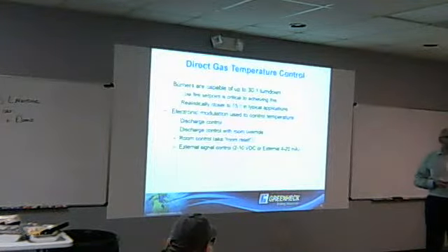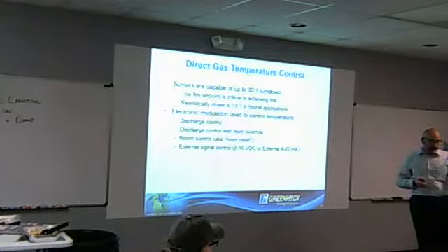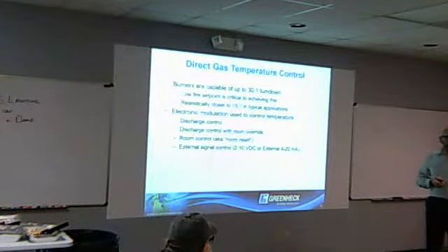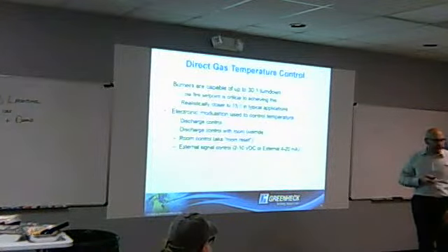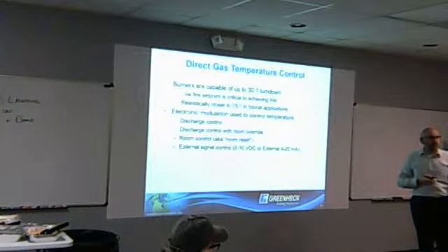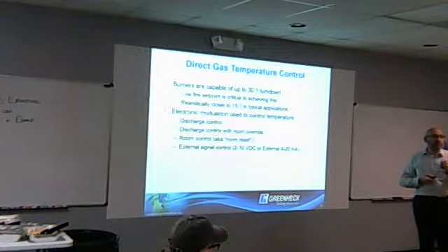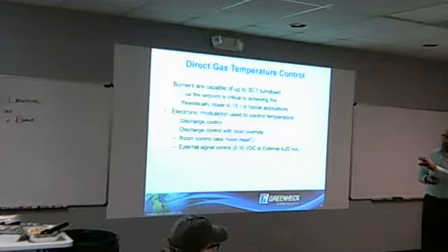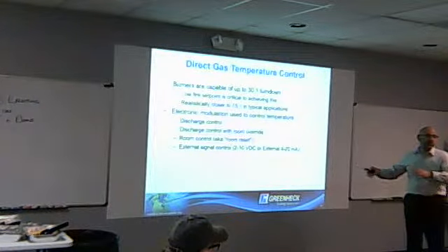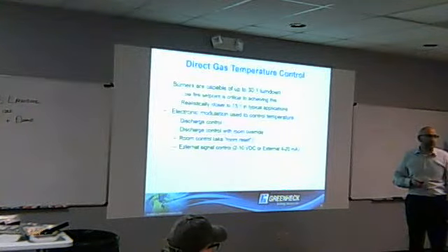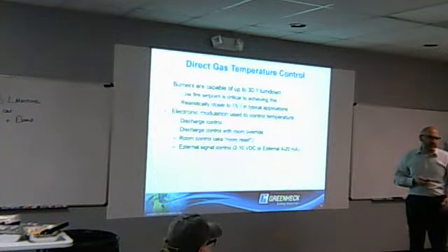I just mentioned 30-1. Okay, so that's usually on the direct fire, correct. On the direct fire. With the indirect fire, you don't get that. Not 30-1, but we can get to 16-1. 4-1 is usually a start, and then depending on the assembly, sometimes I see 10-1. If we have 3 burners, we can get sometimes 8-1, and with 2 burners you get 16-1, 3 burners at 4, 12 to 1. With just one burner, the best you can do was how much? I've seen it anywhere from 4 to 8 to 12. That's fine. Okay.